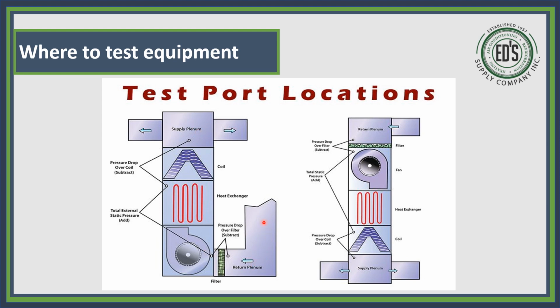So if we could see air, you would see air coming back here, swirling up here, making its way through this filter, going in through this blower motor, coming out, going through the coil here, hitting this and coming right back and hitting the air that's coming back and forth until it starts to do this number and pushes its way out through the ductwork. So you want to be able to test all these. You need to do a test port in your furnace right here and right here. In the blower housing itself, on the other side, leave the filter in place, check it here and check it here, and you can use that reading for your heating reading.